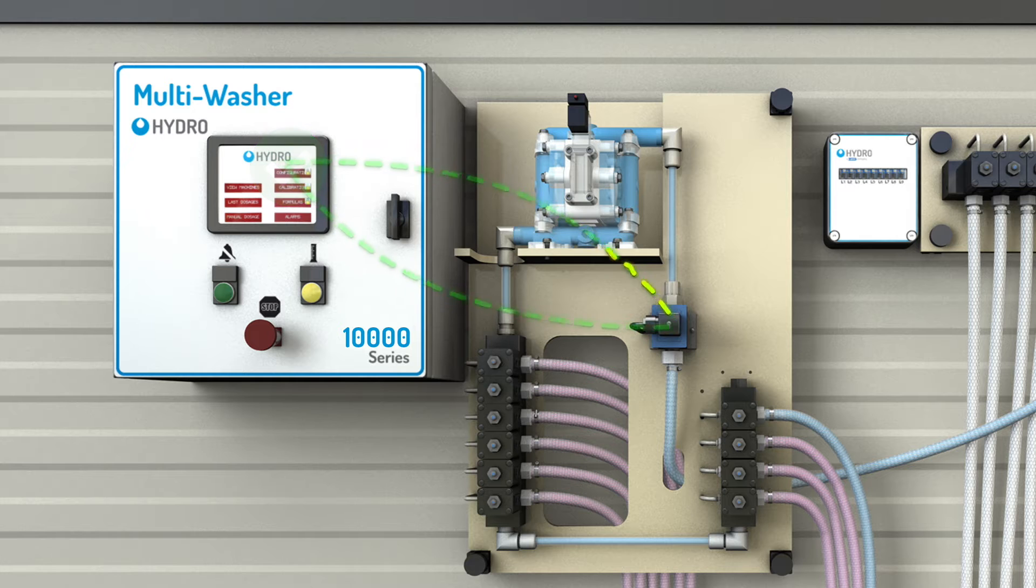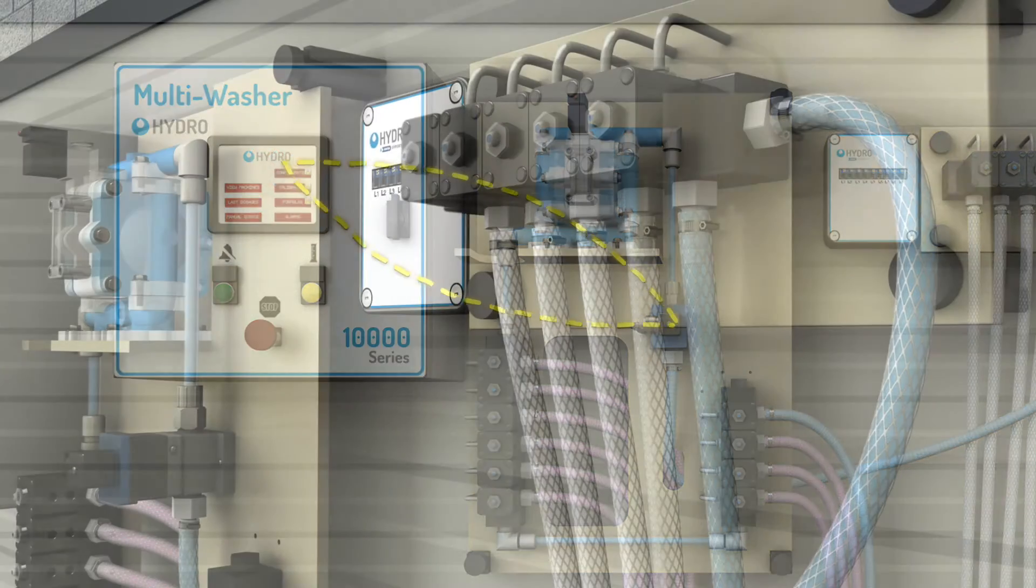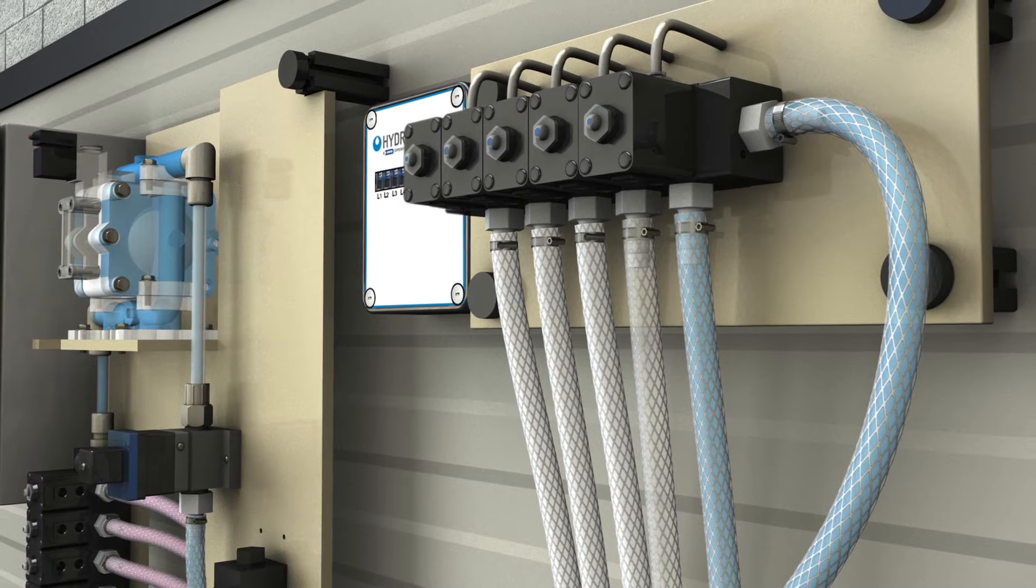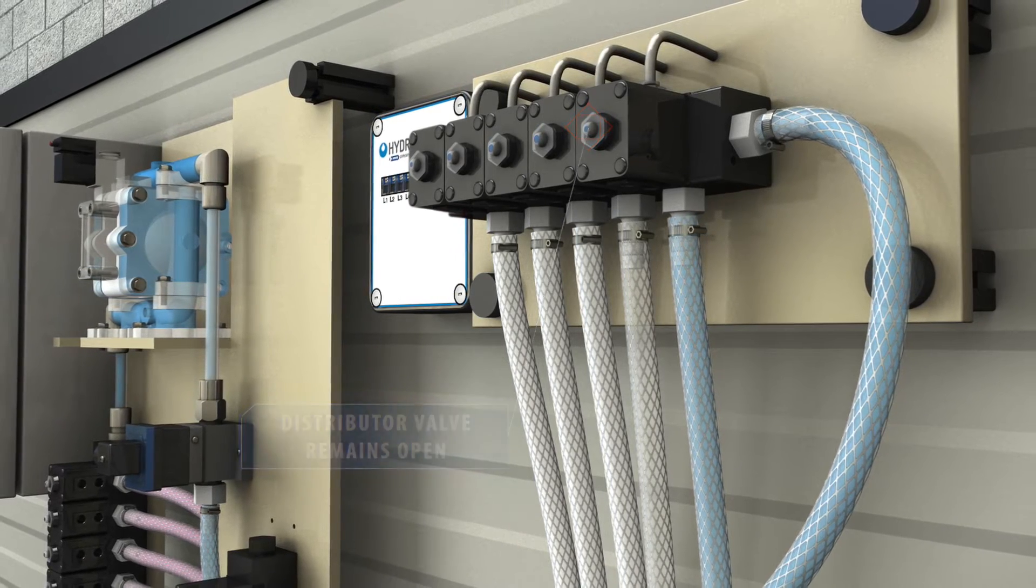If the correct number of pulses are not detected during the test, the test is failed and the dosage is aborted and an alarm is activated. After a successful water test, the distributor valve to the washer remains open while the water valve on the collector closes.